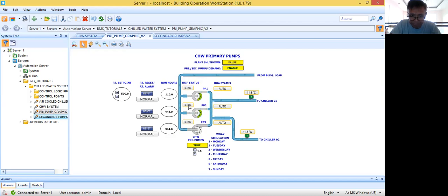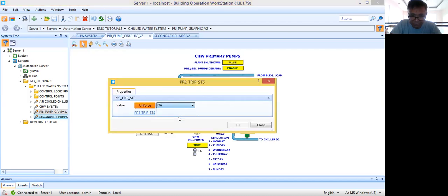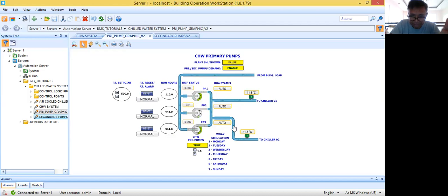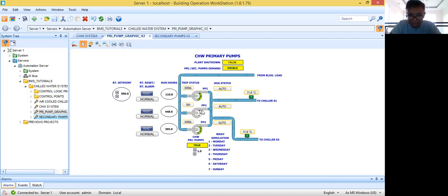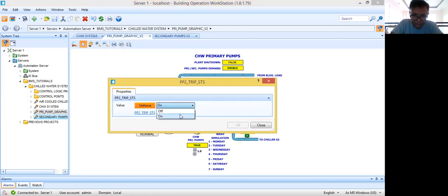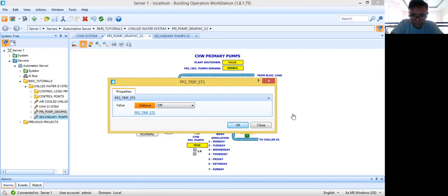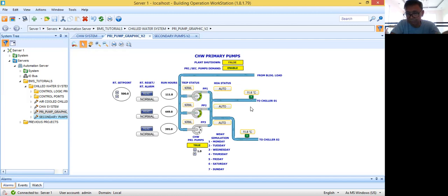How about if pump two trips? Let's say pump two trips. Again, the standby unit — pump three — will kick in automatically. Now there's a trip condition here. Let's remove the trip again and it will go back to pump one and pump two. That will be the response of my control logic program if there is a trip condition on the duty pumps.